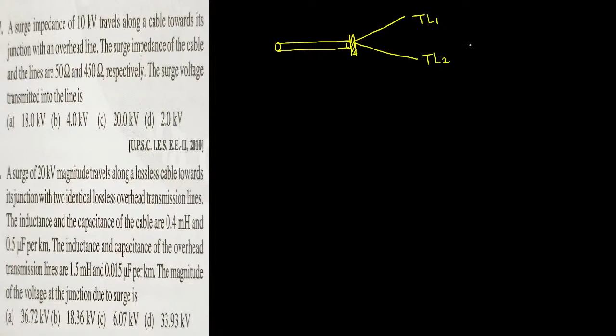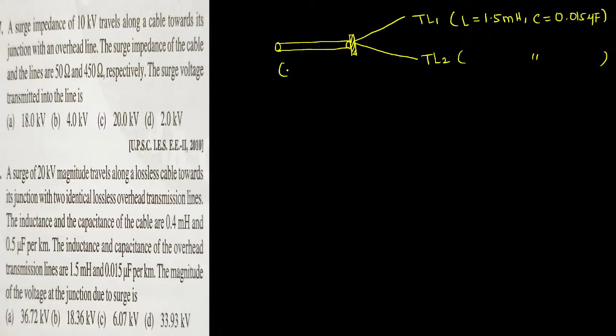Now the inductance of the transmission line is 1.5 millihenry and the capacitance of the transmission line is 0.015 microfarad. That is given. The same data appears for transmission line 2 also, because they didn't separate it. Two identical transmission lines means both data are the same. Next, for the cable it was separately given. Inductance of the cable is 0.4 millihenry, capacitance of the cable is 0.5 microfarad per kilometer. They have given all data per kilometer. Now at this junction, the question is, what is the magnitude of the voltage at this junction? Let us take this as impedance Z2, this as impedance Z3, and this as impedance Z1.